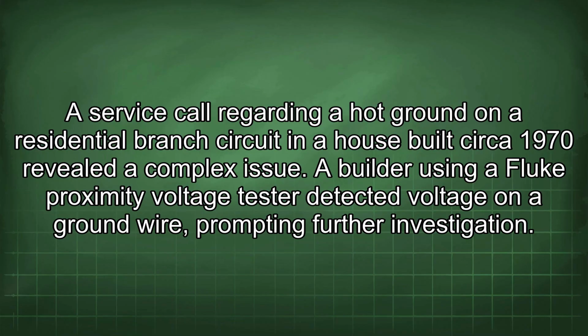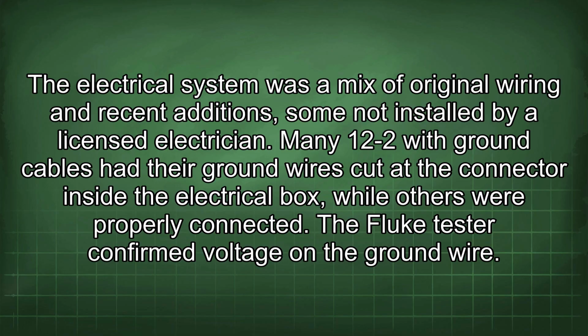A service call regarding a hot ground on a residential branch circuit in a house built circa 1970 revealed a complex issue. A builder using a Fluke proximity voltage tester detected voltage on a ground wire, prompting further investigation. The electrical system was a mix of original wiring and recent additions, some not installed by a licensed electrician. Many 12-2 with ground cables had their ground wires cut at the connector inside the electrical box, while others were properly connected. The Fluke tester confirmed voltage on the ground wire.